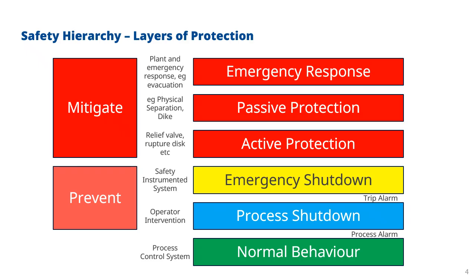So in the safety hierarchy, there are multiple levels of protection. We start with normal behavior, which is the day-to-day operation of a process control system. And within that, there may be process alarms. When an operator needs to intervene in the system, there would be a standard process for shutting down the system called process shutdown, and that may also lead to trip alarms. Where events go beyond normal operation is when we get into the safety instrumented system stage, and that's where an emergency shutdown is required. So these are preventative measures.